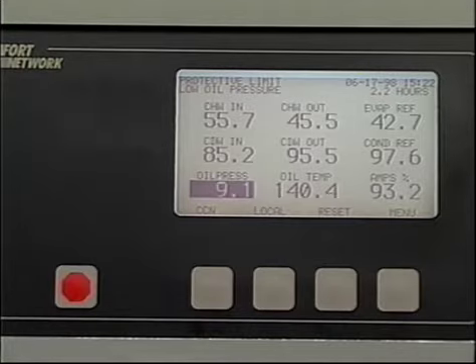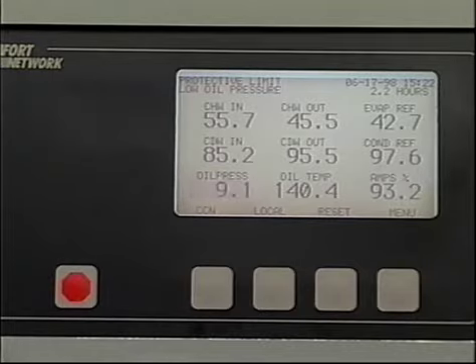Whenever an alarm occurs, the LID default screen will freeze and display the condition of the chiller at the time of the alarm. This is useful for troubleshooting. Be sure to record the data before pressing any of the soft keys. The alarm light at the left of the display will activate whenever an alarm exists to call attention to the condition. When the problem has been corrected, the chiller can be restarted by first pressing the reset key and then pressing either the local or CCN key, depending on whether the chiller is under local or remote control.